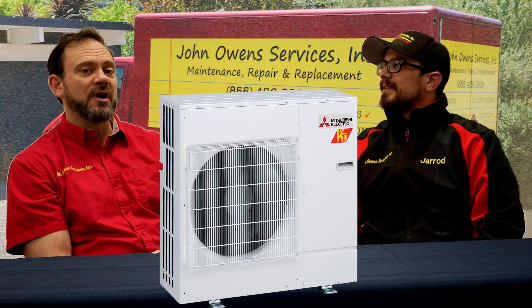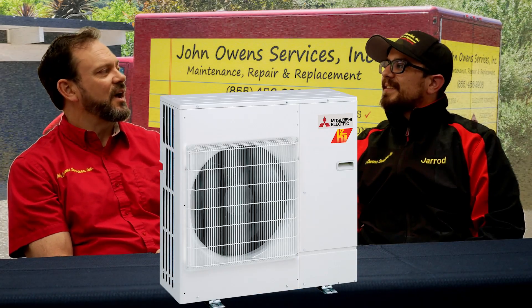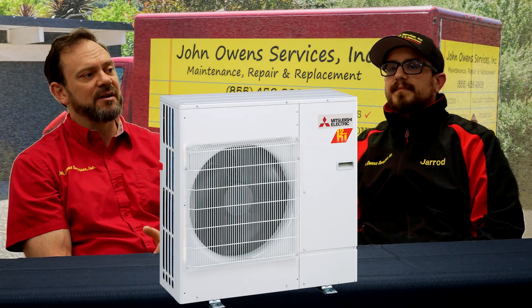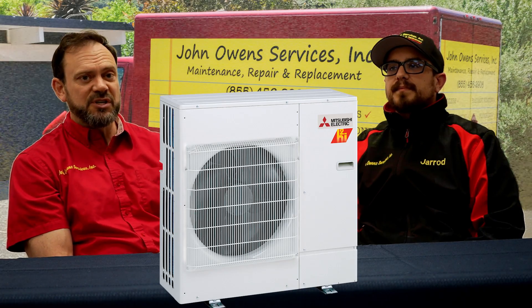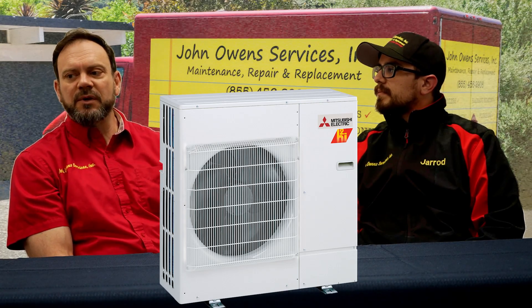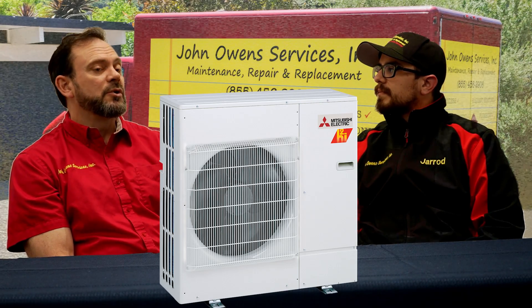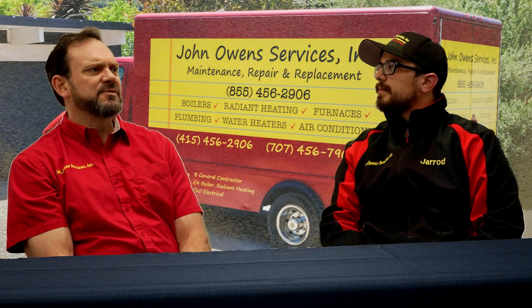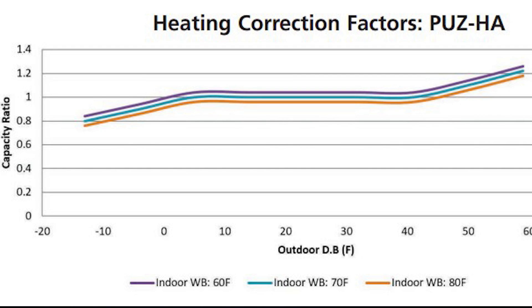If you don't want the gas system or the heating element because you'd be losing efficiency, we go to the newer high-tech option: it's called hyperheat. Not many manufacturers offer it — as far as we know, only Mitsubishi does. It works great down to really, really low temperatures — even negative degrees, no problem — and at 100% capacity down to lower than 10 degrees.